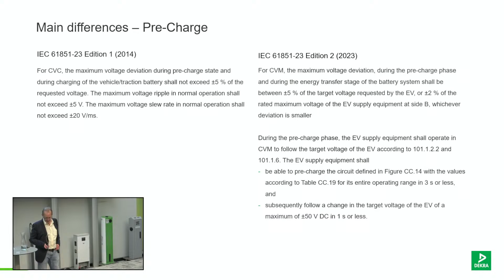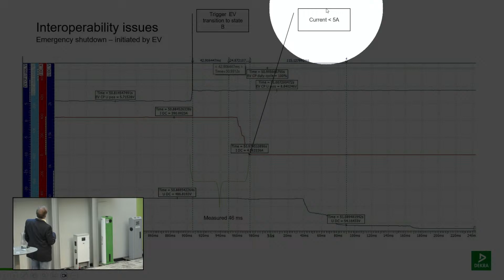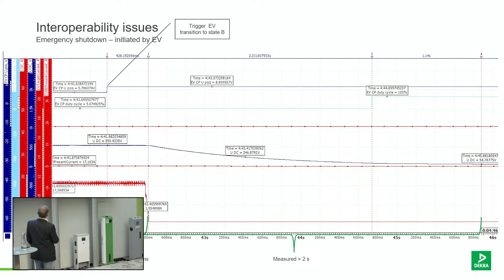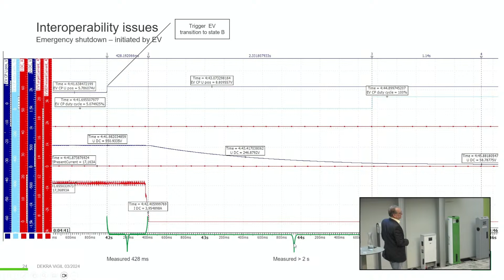So also here, if we look, let me skip that, let's go to this one directly. If we look at what we see on the market, we see times of 46 milliseconds until it actually is triggered, and we have times of approximately 40 milliseconds before the current is below 60 amps, and another roughly 100 or so milliseconds before the voltage will drop below 60 volts. So also that, in fact, could be a safety hazard. Also here, I think that is even more extreme. So the trigger time and the reaction time of reducing the current below 5 amps was like 428 milliseconds, and for the voltage it was about 2 seconds. Too dangerous, very clearly too dangerous. Should not be the case.